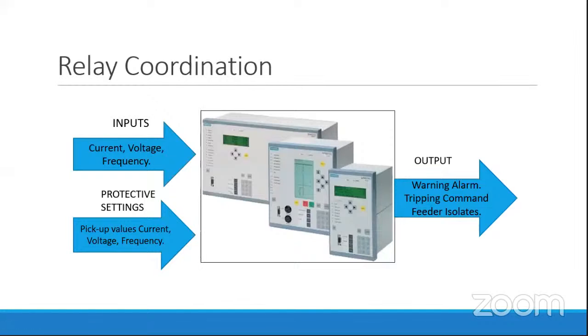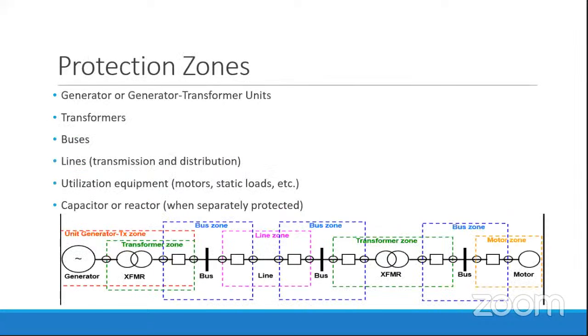Now let's move on. Okay, this protection zone. Before going further to relay coordination, let's have another basic idea from here. As we are giving protection to every equipment, it is known as unit protection for every equipment like a motor, transformer, generator or line. It will have unit protection. But now, as we are talking about relay coordination, relay coordination should be done from downstream to upstream. Here the downstream will be this motor and the upstream will be this generator.